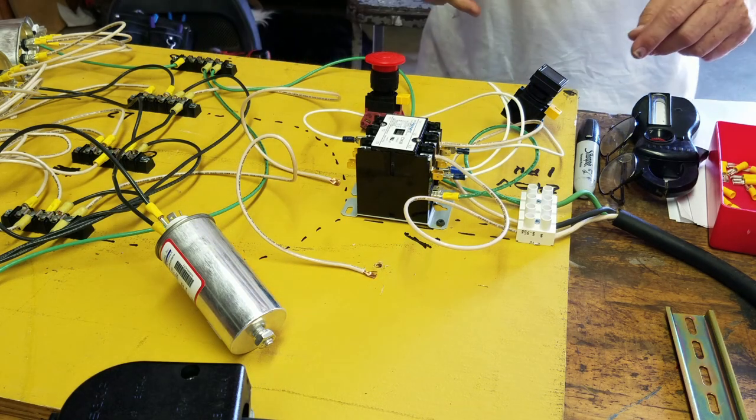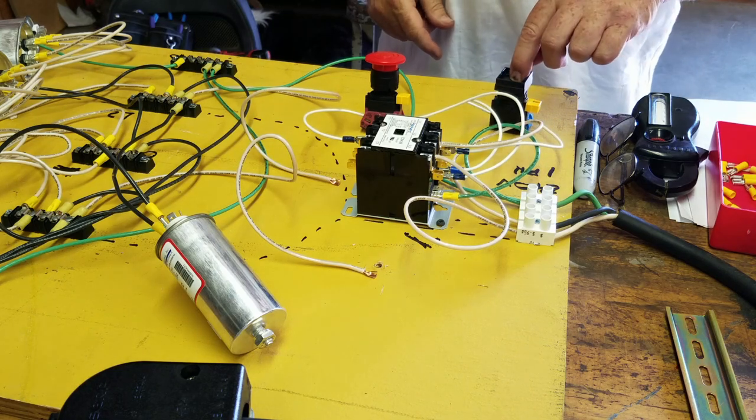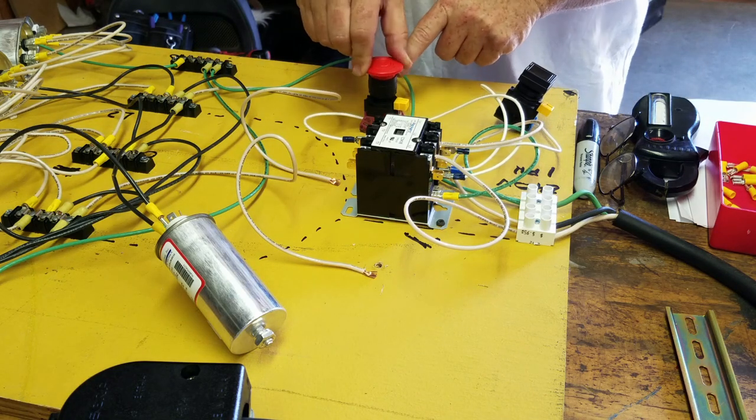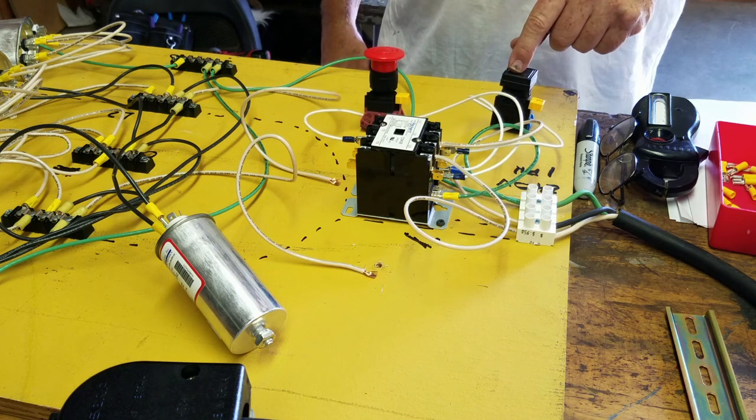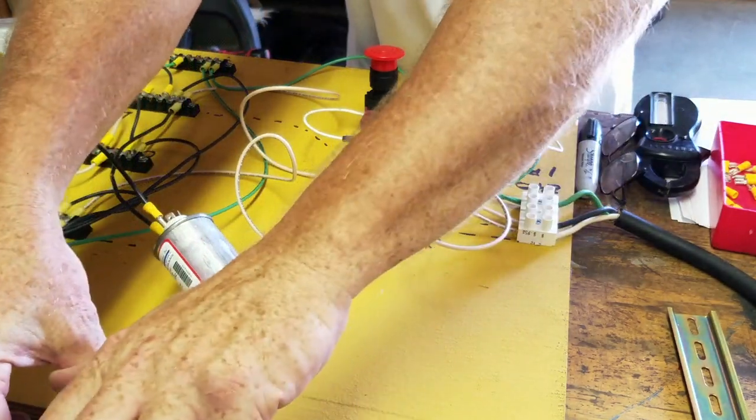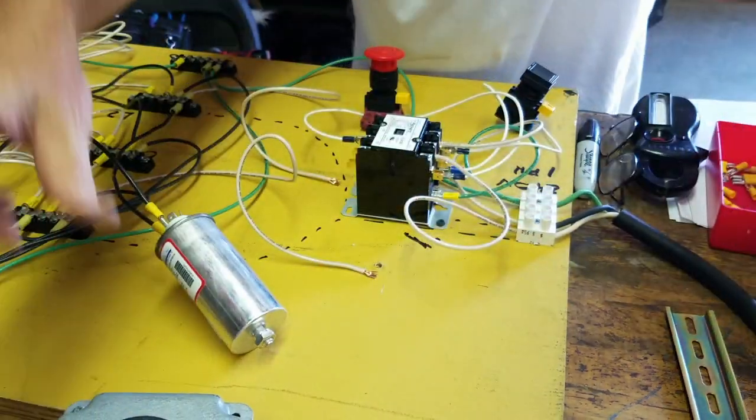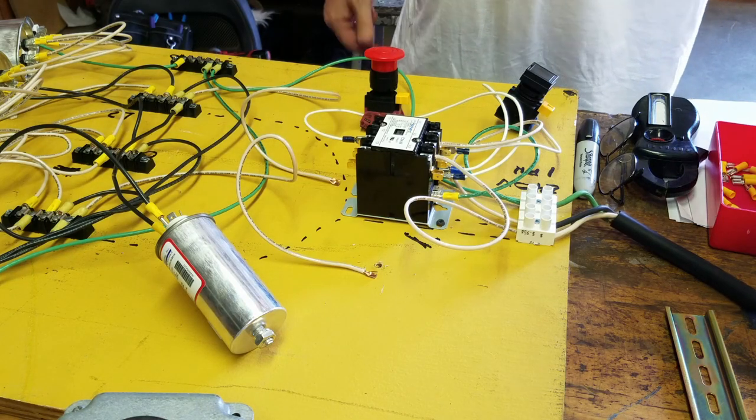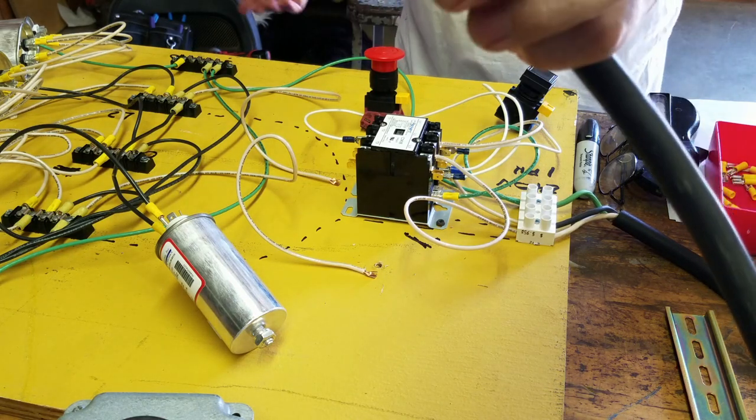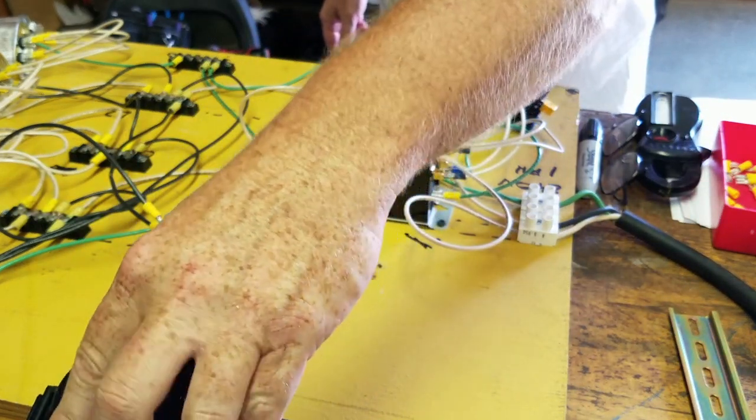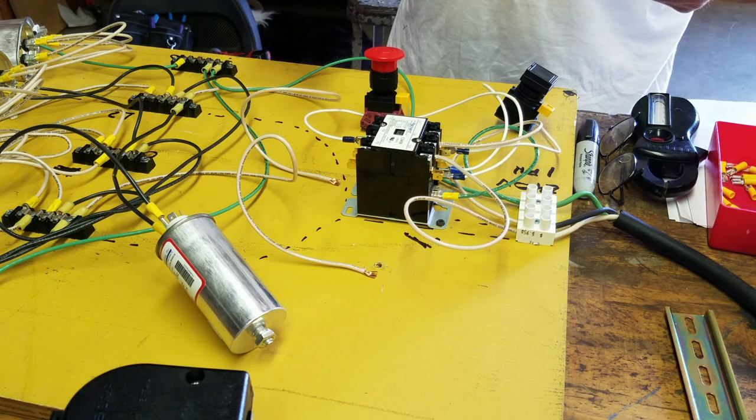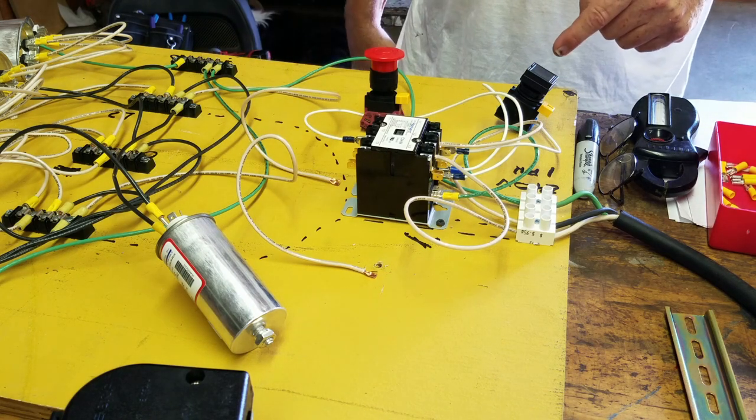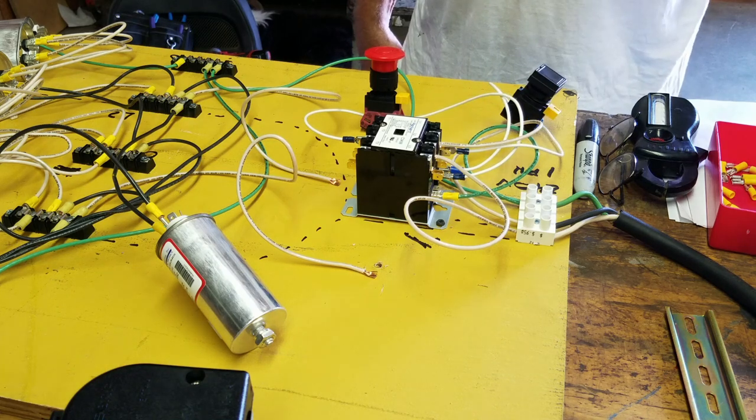We're going to demonstrate a power outage. First, we're going to start the machine. Oh, E-stop wasn't off. We're going to start the machine. Machine's running. The power goes out for whatever reason. Stormy night. Power goes out. Oh, you heard the relay trip. Ten minutes later, or four days like around here, the power comes back on. Nothing happened. There's no power over here to energize it. I've got to physically press the button again. There it is.